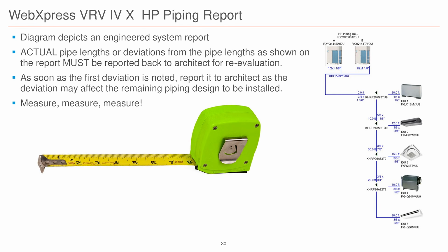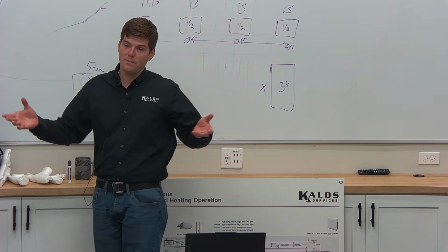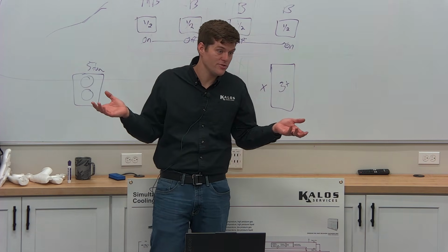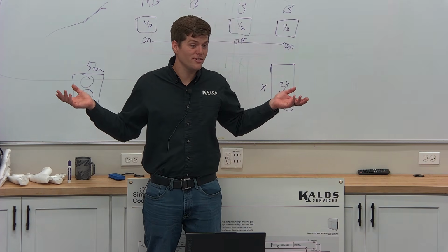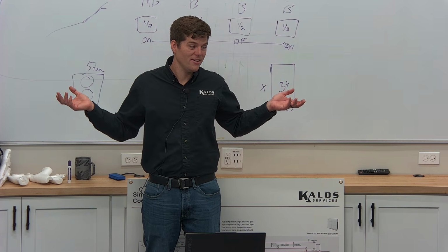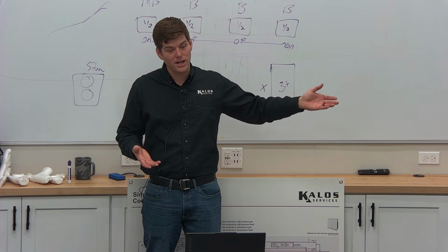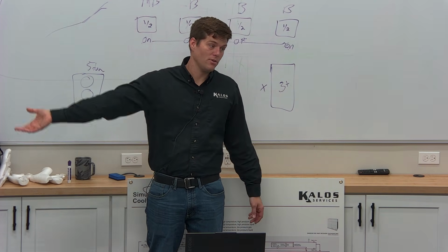If I'm 10 feet off in 15 different places, that's 150 feet. Let's say it's 150 feet too much, right? Let's say that I only have 100 feet of piping, but I accidentally calculated an extra 150. Now the system's overcharged, right? And you have issues with oil getting back to the outdoor unit because the compressor can never ramp up, because it's going on high pressure step down.